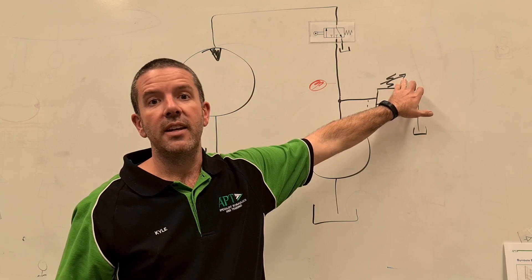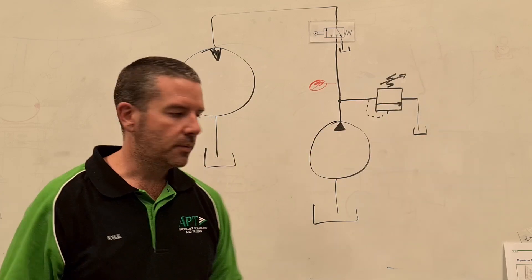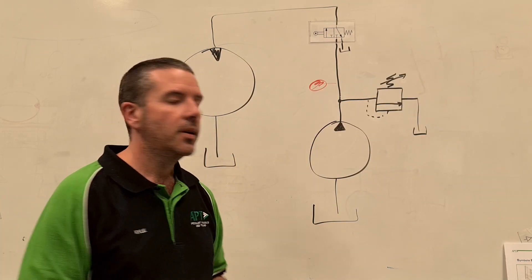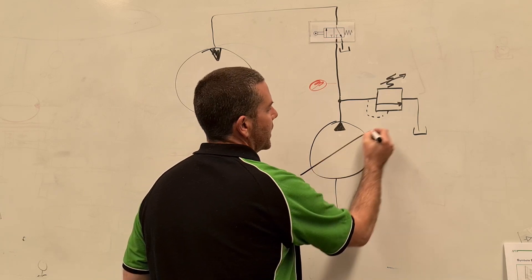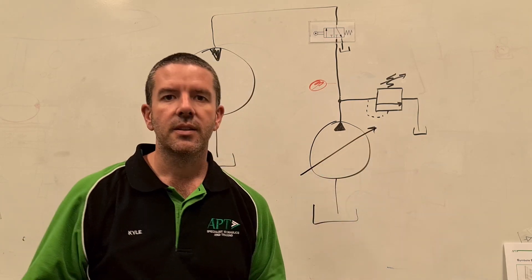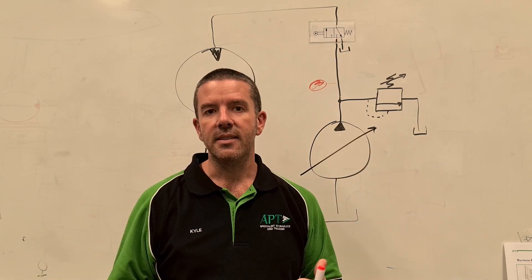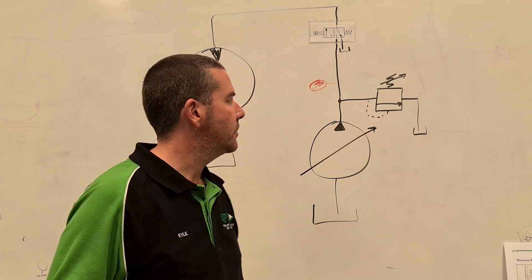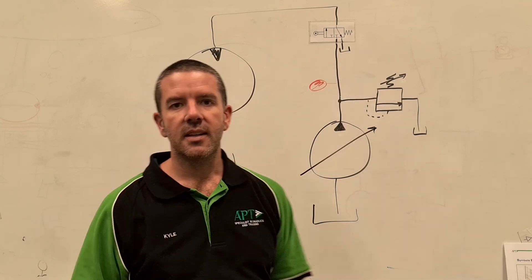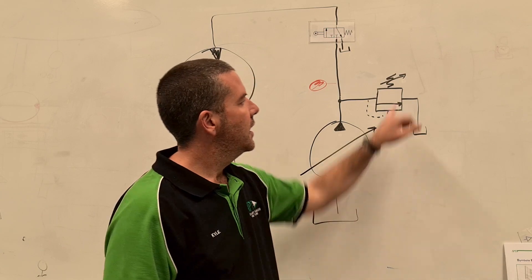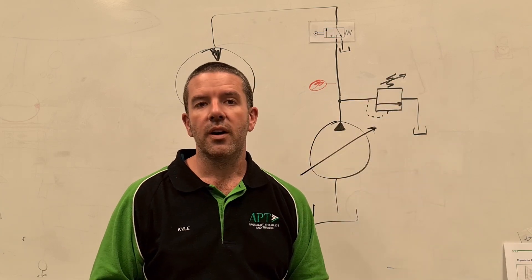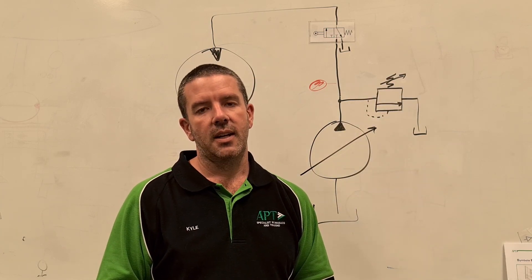A diagonal arrow through anything at all means that it is variable. So in the case of the pump, if we've got a variable pump, it might have an arrow through it like this, which means the output of it is variable or the displacement of it. So in this particular case here, there's a spring on top of this valve and that spring is adjustable via an adjuster, and that affects the setting of that valve.